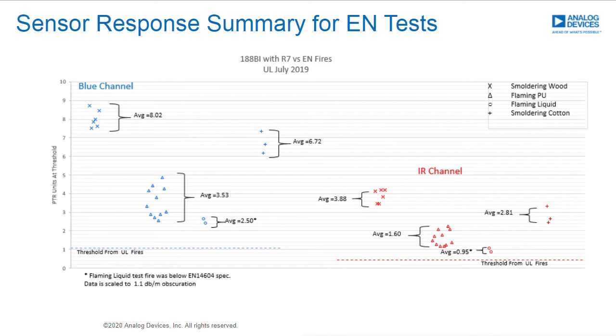And basically what this shows you here is that the threshold that we've set based on our UL testing, based on that flaming polyurethane level, is still below all of the EN fire types. So basically, with a single smoke detector and setting your threshold based on the flaming polyurethane test from the UL standard, you're able to pass all of the UL 217 specs as well as all of the EN specs.